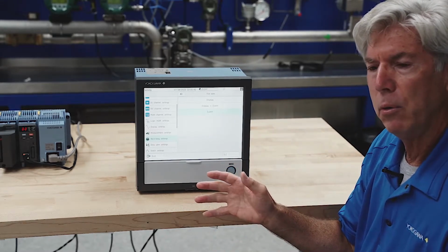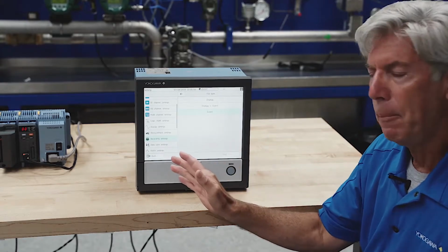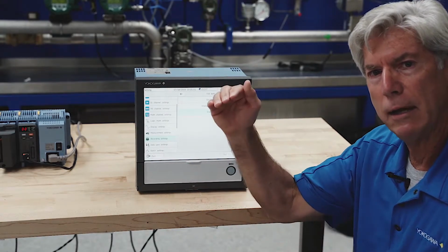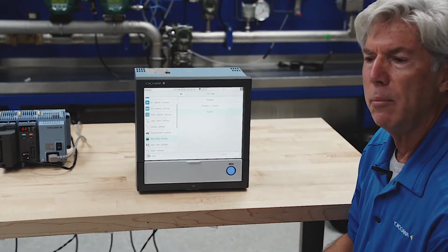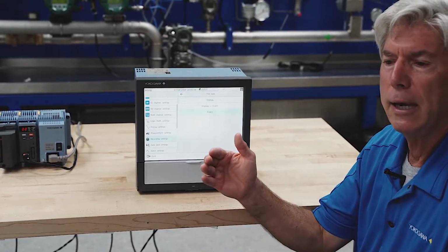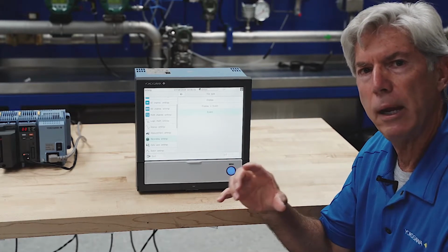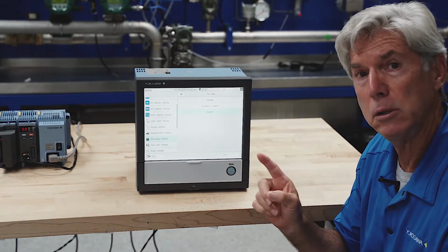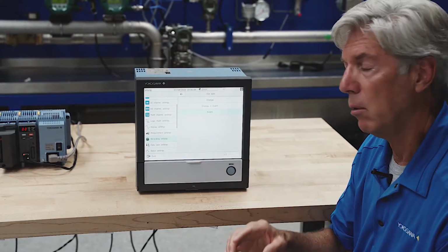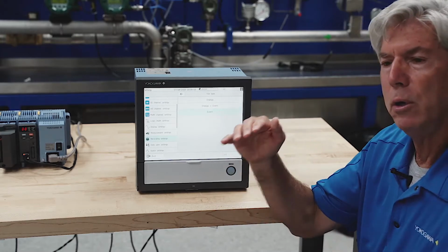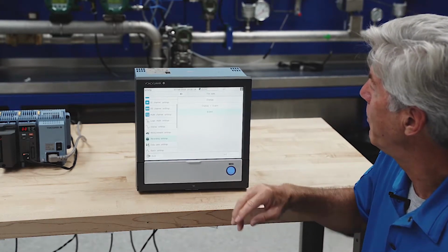If you're logging in display mode, you'll log 2 values for every pixel movement across that chart, the maximum and the minimum value that channel saw. You might be logging a value every second, but during that 1 second in time, that recorder was sampling every 100 milliseconds. So during that 1 second, there were 10 samples taken on that particular channel. What it saves in display mode is the highest value and the lowest value out of those 10 samples, okay?